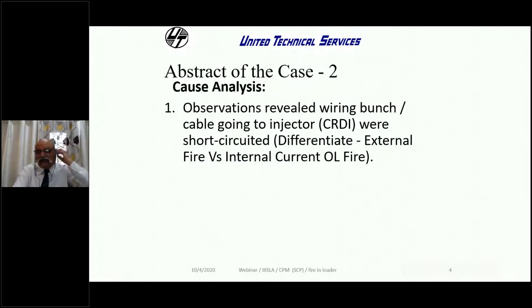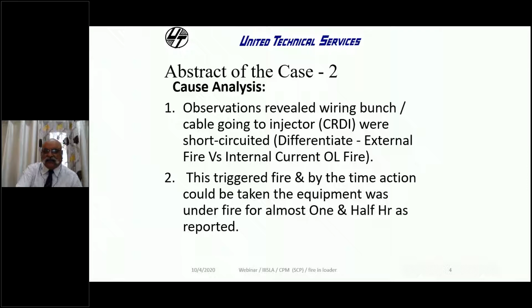Now, as I said, we have to differentiate. There may be external fire which has affected the cables or wiring, or there may be an internal heavy flow of current, overload current, which has triggered a fire. By the time action could be taken, the equipment was under heavy fire. So proximate cause is electrical short circuiting in the CRDI wiring loom.